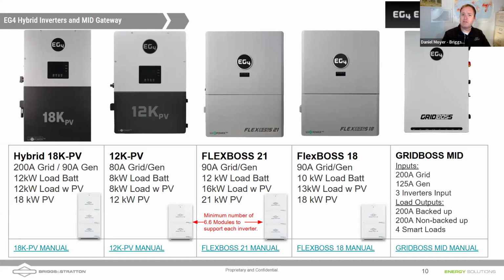And then the FlexBoss 18 and 21, right? They still have the transfer switch or the MID, the microgrid interconnection device built in, but they only take in 90 amps. So that's why in a lot of situations, we are going to want to pair that FlexBoss with the Grid Boss.